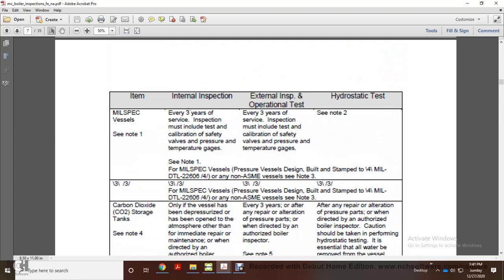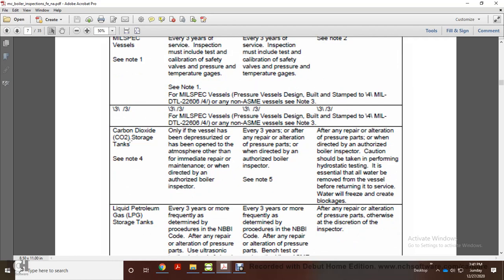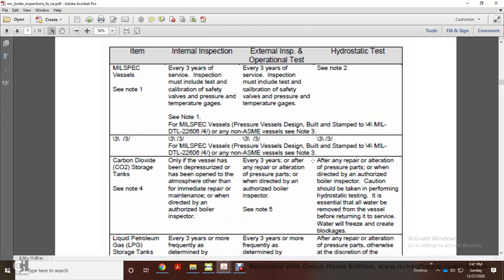Mil-spec vessels: every 3 years, inspection must include testing and calibration of safety valves and pressure and temperature gauges. Every 3 years, service inspection must include testing and calibration of safety valves, pressure gauge, temperature gauge, and hydrostatic test. CO2, carbon dioxide storage tanks: only vessels to be depressurized, having been open to atmosphere other than for immediate repair or maintenance, or when directed by the authorized boiler inspector, every 3 years, after a repair or alteration of pressure parts, or as directed by the authorized boiler inspector. Hydrostatic testing after repair or alteration of pressure parts, as directed by an authorized inspector.